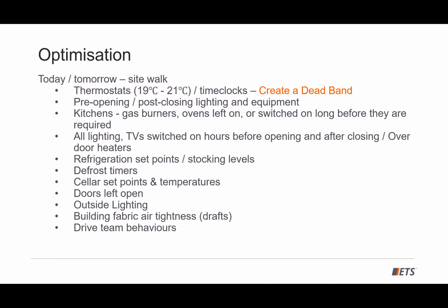Defrost timers - a lot of equipment for frozen storage has defrost timers set to defrost on average 6 times a day. You can look at that equipment and work out what defrost is actually needed. During defrost the refrigeration element stops, electric heaters come on within the unit to do the defrost, then go off again and refrigeration comes back on. If you reduce the amount of defrost needed, you reduce the electrical energy for the timers and the defrost, and reduce the refrigeration duty needed to bring the equipment back to set point temperature. So it's always good to look at that.